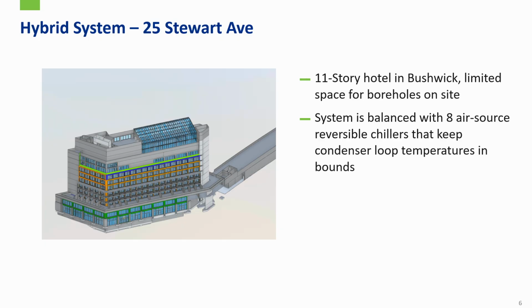Those chillers monitor the condenser water temperatures, and when they get out of bounds, they kick on and bring it back in. That essentially freezes the thermal drift at whatever level it's at in that specific year, so you don't get year-over-year runaway.